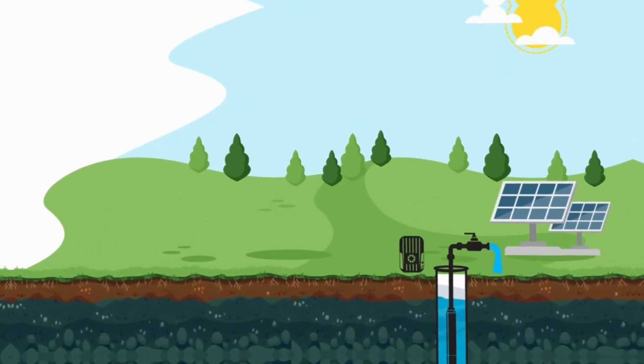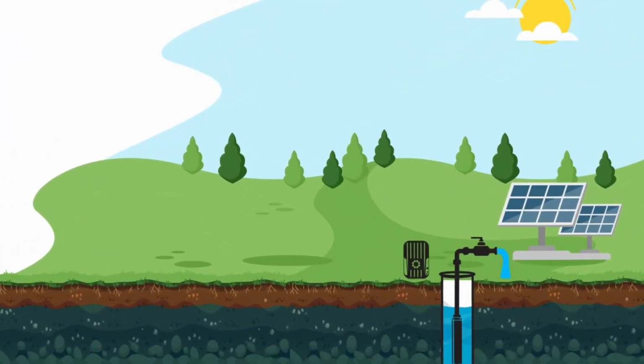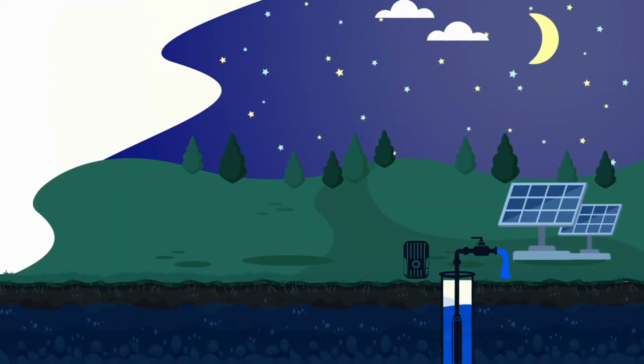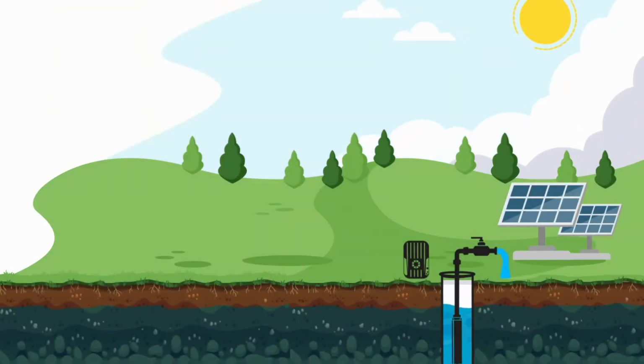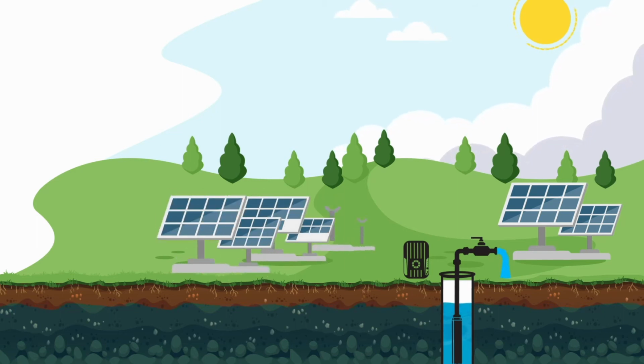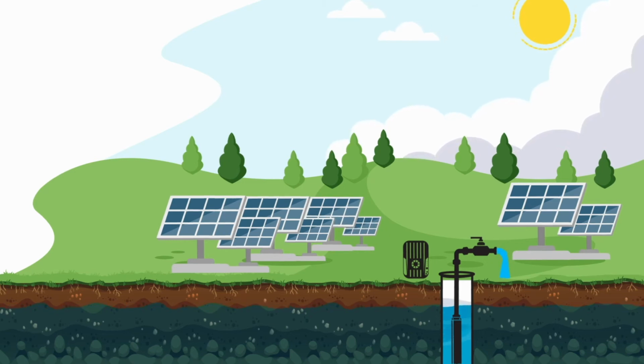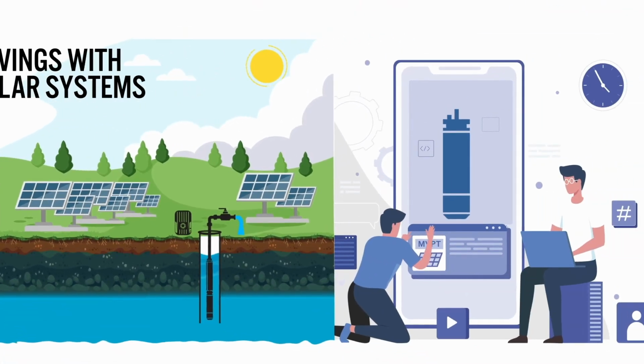In solar applications, you have even more clear advantages when using the Franklin HESS. The solar radiation tells you how much energy you can get from the actual sunlight. Each day, you only have a certain window of time where you have enough sunlight to keep your system running at full speed. It depends on your location and changes with the season, the time of day, and the weather conditions. The solar system must be carefully sized to achieve the desired system performance. This depends on the number of solar panels and how well your solar drive controls motor and pump. The MPPT algorithm of the Franklin HESS maximizes the system performance.